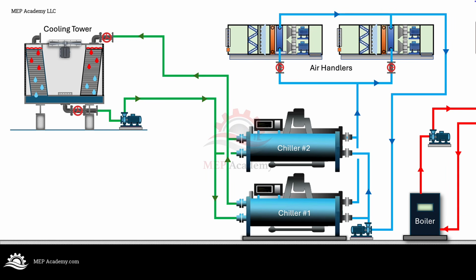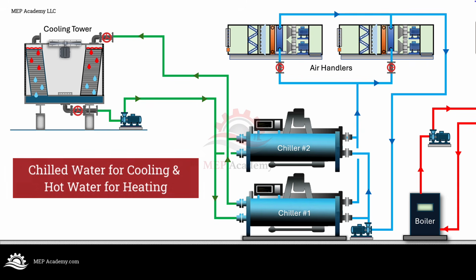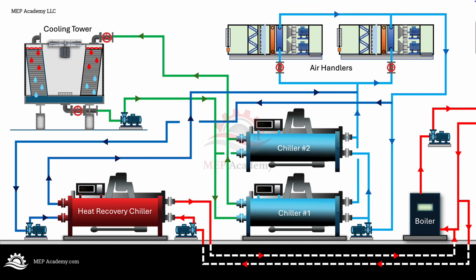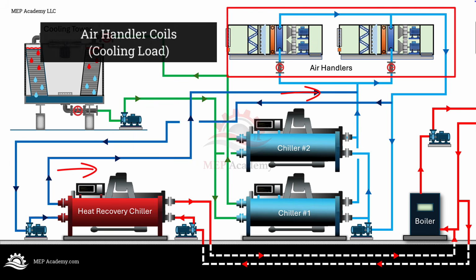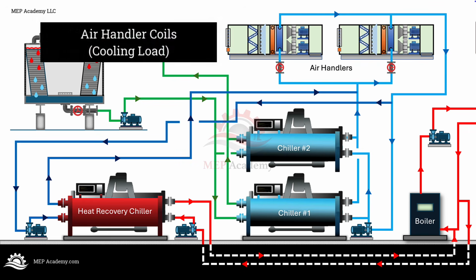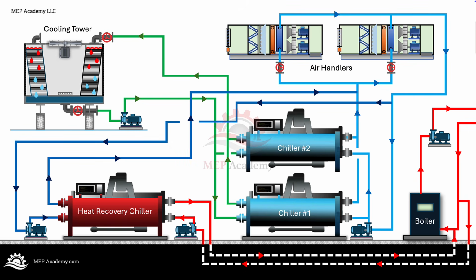In this case, the heat recovery chiller directly produces chilled water for a cooling load and recovered heat for a heating load. This is probably the easiest application to understand. The chilled water leaves the heat recovery chiller and flows to a cooling load. That cooling load could be an air handling unit, a data room, an electrical room, a laboratory, an interior zone, or another piece of equipment.